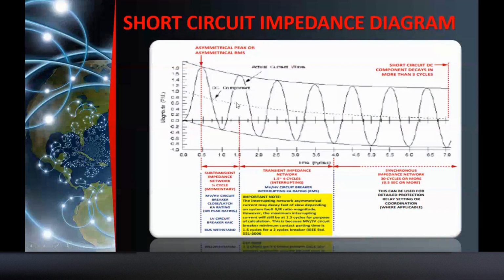So this one, I just want to share you about the subtransient impedance, usually 1/2 cycle. Ito yung reference mo dun sa fault. I mean, kung 0.5 or 1/2 cycle, yan ang ginagamitan natin ng subtransient reactance. 1.5 to 4 cycle, that is the transient impedance, and the synchronous, which is going to the steady state.